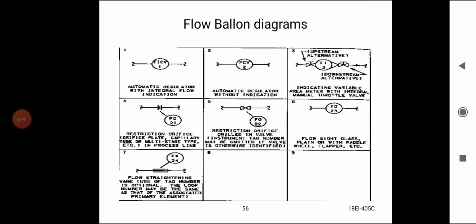Flow balloon diagrams: flow indicator and control. Automatic regulator with integral flow indication, flow indicator and control valve, flow control, automatic regulator without indication, flow indicating variable area meter with the integral manual throttle valve, flow indicator.